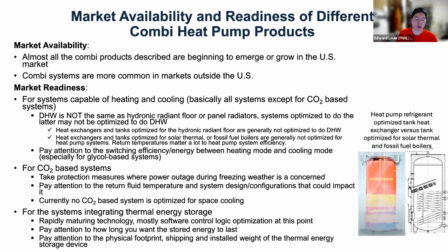But in the heat pump water heater space, those tanks have figured out how to use refrigerants to heat domestic hot water to 130, 140 degrees while still maintaining reasonable liquid line temperatures. So we hope that in the near future, these combi systems that use refrigerants in a split manner would adopt tank designs and heat exchanger designs that have already been figured out in the unitary heat pump water heater space. Here's just an example in the lower right. The tank on the far right is one that's optimized for solar thermal and also for being paired with fossil fuel boilers. That heat exchanger, as you can see, just doesn't have quite the surface area as the one on the left, which has very fine refrigerant lines wrapped around the tank.